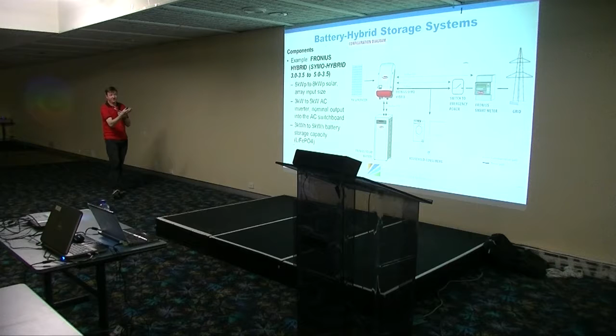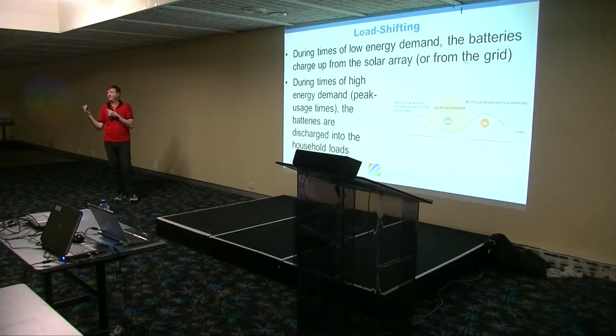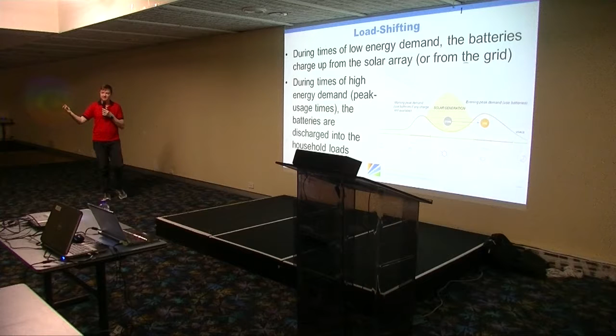We talked about load shifting before. It doesn't seem to be a problem here because you have a set rate day and night. But if you didn't, it has the ability—for both UPS and hybrid—to charge the batteries at a predetermined time when the energy is cheaper, which will be off-peak, certain times in late morning and certain times mid-late afternoon. And then use that stored energy during peak times, which would be 4 to 7 p.m. at night, for example, and the morning peak if there's any left over.